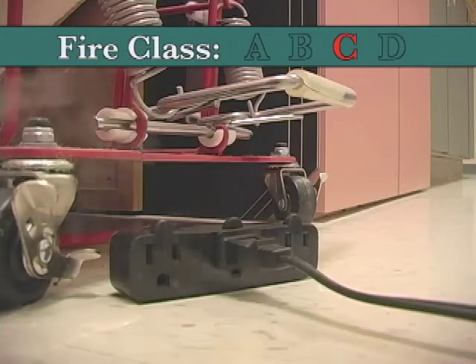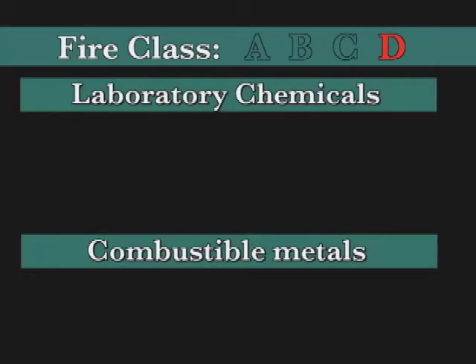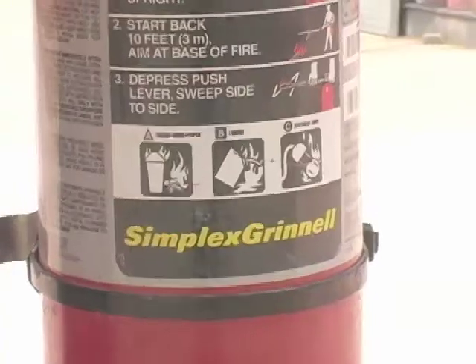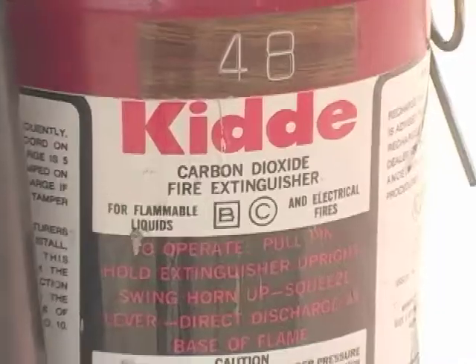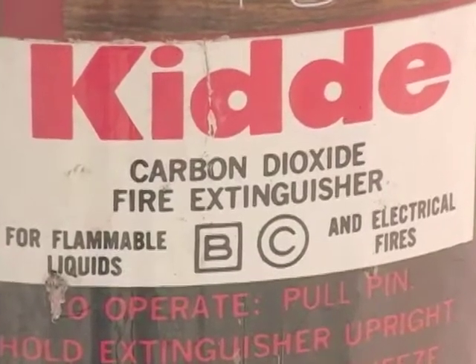Class C fires are electrical, happening in appliances or other electrical equipment, in wiring, circuit breakers, and outlets. Class D fires are commonly found in chemical laboratories. They involve combustible metals such as magnesium, titanium, potassium, and sodium. The label on the extinguisher will tell you which fire it is designed to put out.